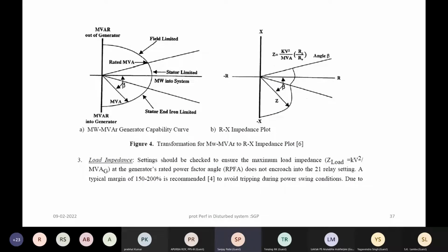If you see the capability curve, this is the generator capability curve which we have shown. We have seen it yesterday also. This is the active power, this is MW axis, this is MVAR axis. Normally, we are operating in this quadrant. Now, if this same capability curve you have to represent in terms of impedance diagram, that is R and X, then it will look somewhat like this, the impedance plot.